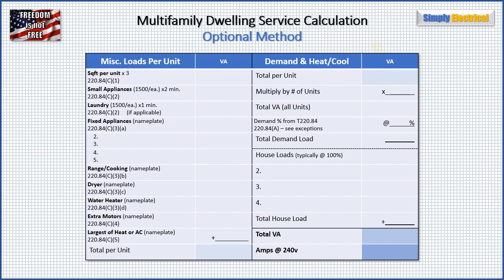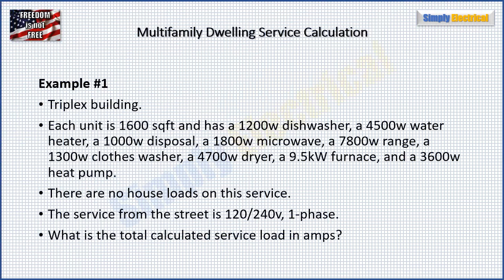Okay, let's get to our examples. Example one is a triplex where each unit is 1,600 square feet, has a 1,200 watt dishwasher, a 4,500 watt water heater, a 1,000 watt disposal, an 1,800 watt microwave, a 7,800 watt range, a 1,300 watt clothes washer, a 4,700 watt dryer, a 9.5 kW furnace, and a 3,600 watt heat pump. There are no house loads, and it is a 120/240 volt single phase service. What is the total calculated service load in amps?